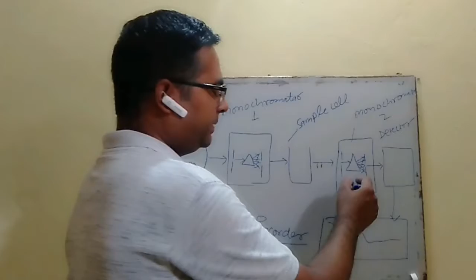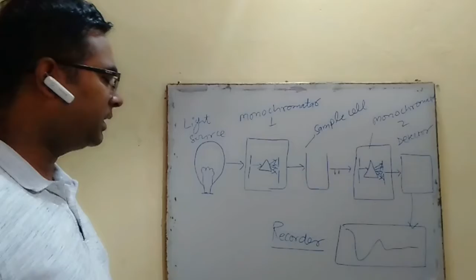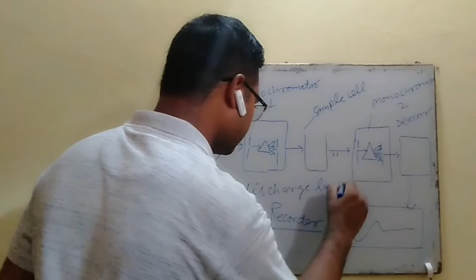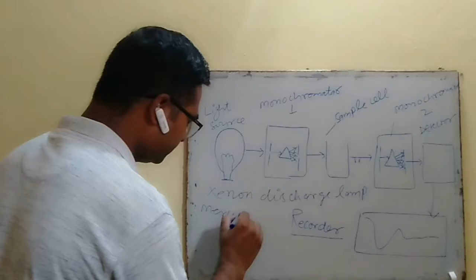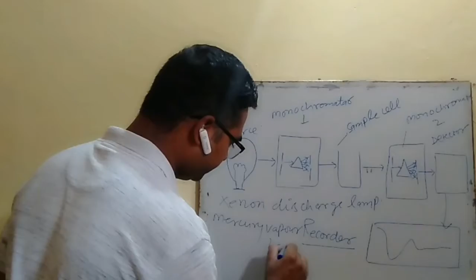The basic sources used in UV visible spectroscopy, like the tungsten lamp, deuterium lamp, and hydrogen lamp, cannot be used in a spectrofluorimeter, because the intensity emitted by these sources is very low. Therefore the best lamps used in a spectrofluorimeter are the xenon discharge lamp and the mercury vapor lamp. A high pressure xenon discharge lamp is used as a source, but one major disadvantage of the xenon discharge lamp is that the oxygen present in the lamp may be converted at high temperature into ozone, which is a toxic material. So the ozone that is generated in the lamp may be absorbed by using charcoal in the lamp.